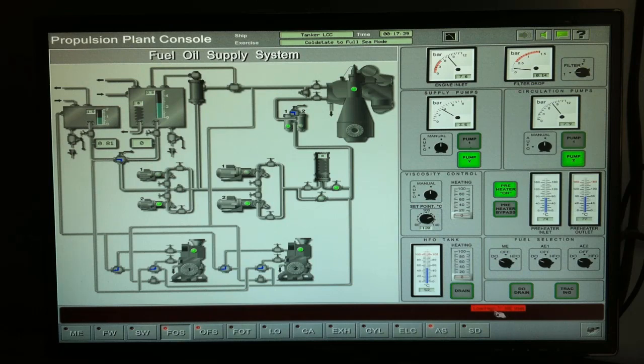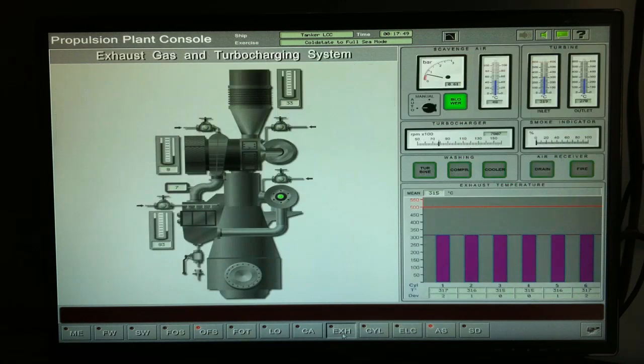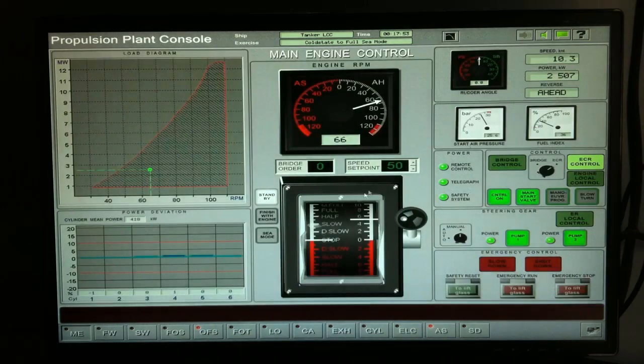So we have an alarm on the main engine fuel oil inlet temperature. All you need to do is adjust the viscosity control to automatic. Then supply pumps set to auto, circulating pumps to auto. Then proceed back to your exhaust. Raise the telegraph again.